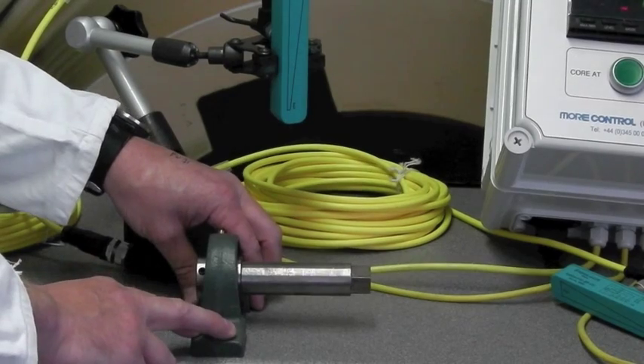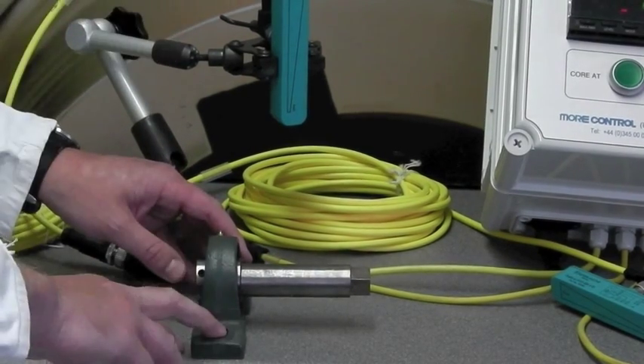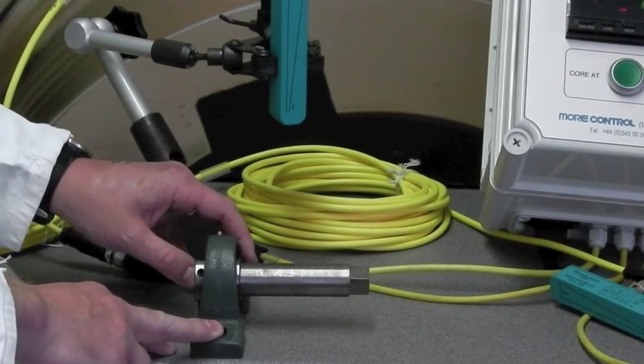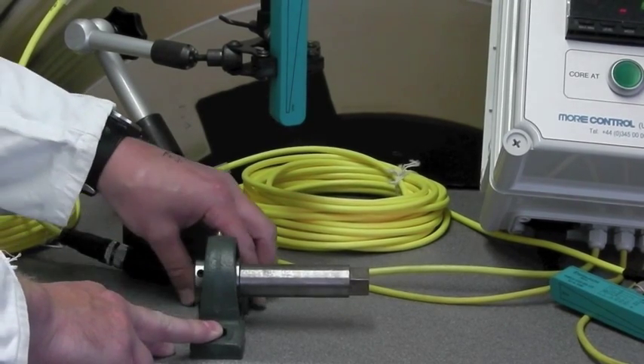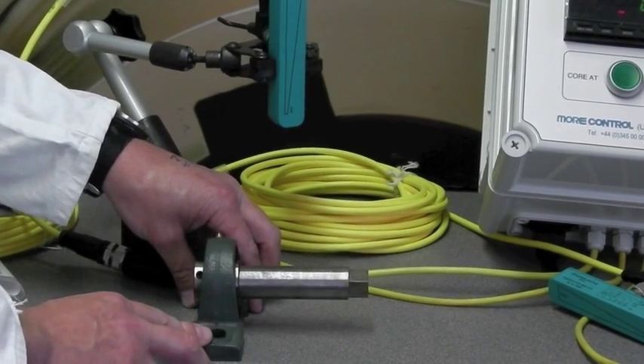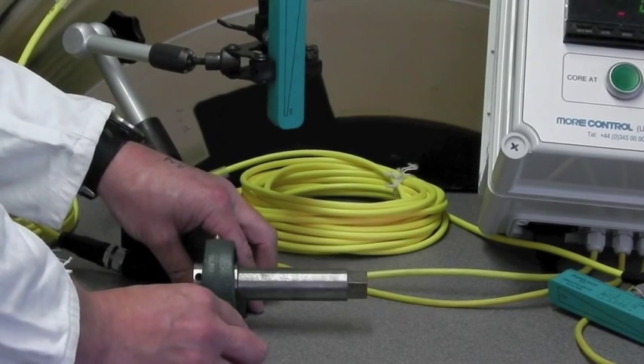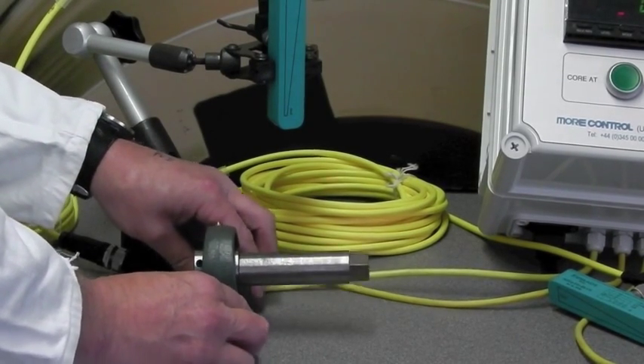What they're currently using is a lead screw with a handle and a mechanical numerical display. What they find is they get a lot of backlash in that system. So as they're changing the numerical display, it may not have so much relevance as to the height of the bearing.